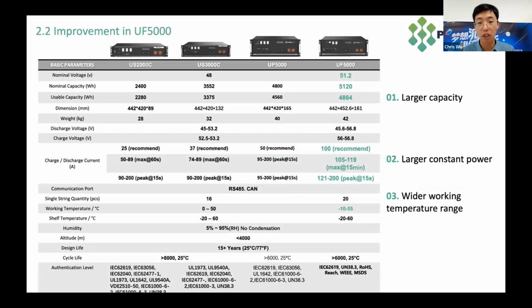And for UF5000, it is higher than the other batteries, which means it has a larger capacity. About the weight, it is also from small to large in response to the usable capacity. Then let's talk about the discharge voltage and charge voltage. For 48 volt batteries, we can discharge them to 45 volts, and the upper voltage is 53.2 volts. But for UF5000, it can have a wider range for discharge and a higher charge voltage.